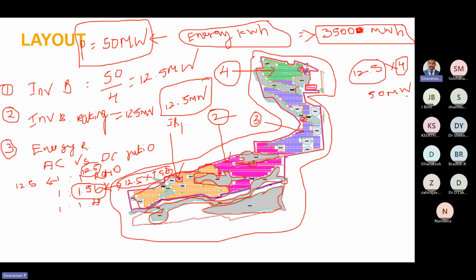And at the same time we have to meet the energy requirement for the particular year. In this example it is 3500 megawatt hour. So in order to meet this 3500 megawatt hour, we have to increase the DC capacity. Why? I already told you how solar will operate.